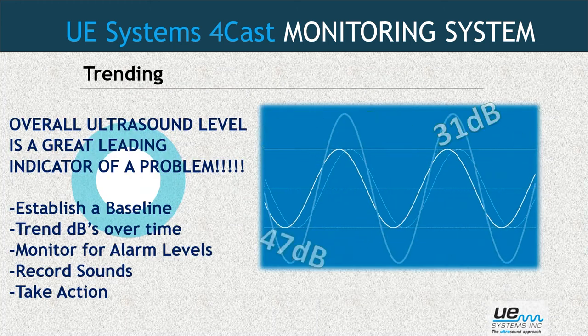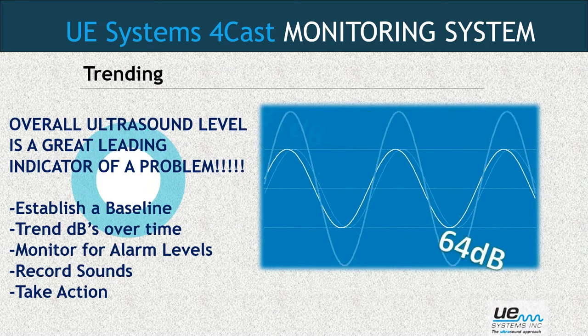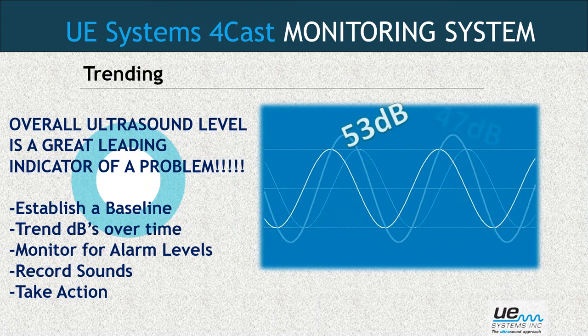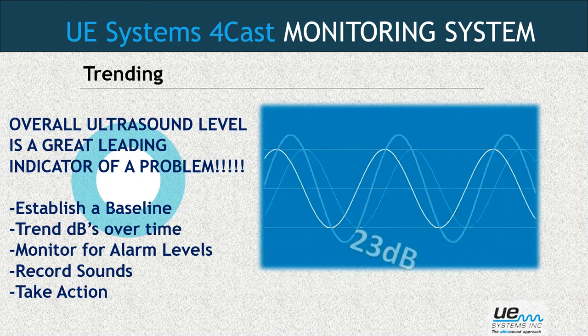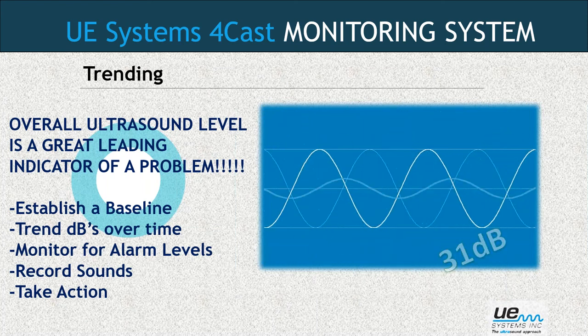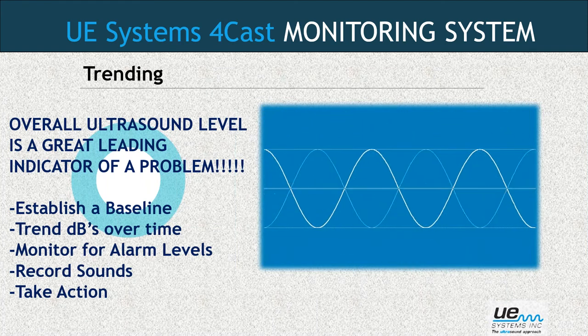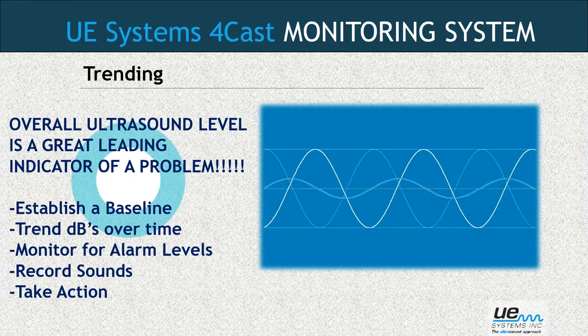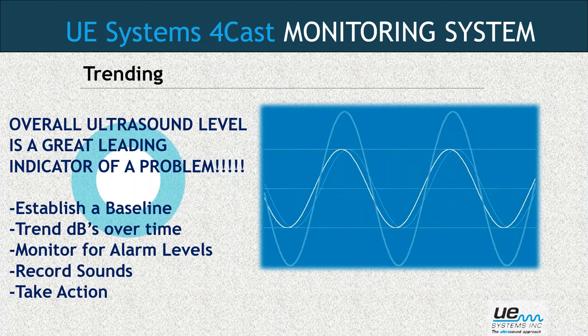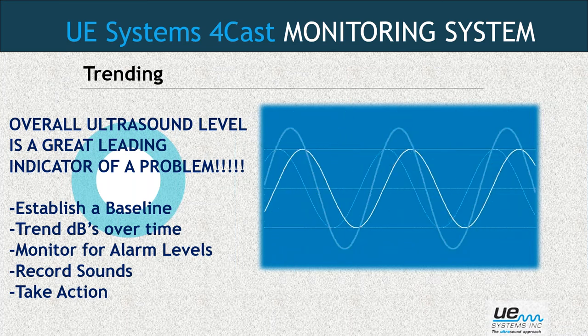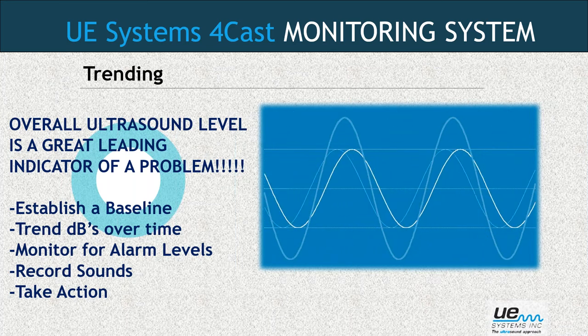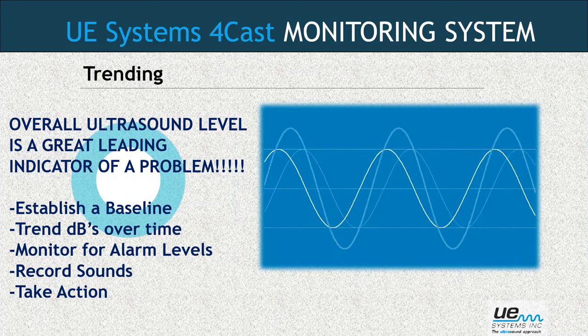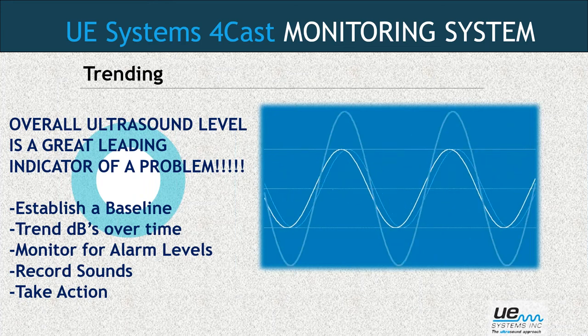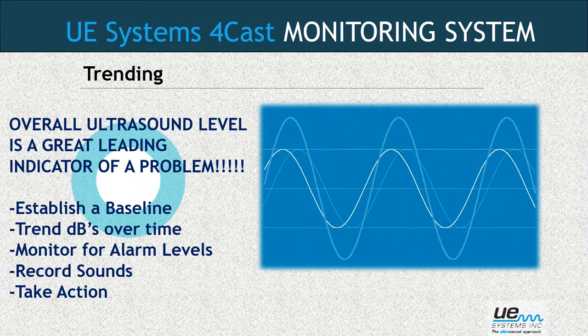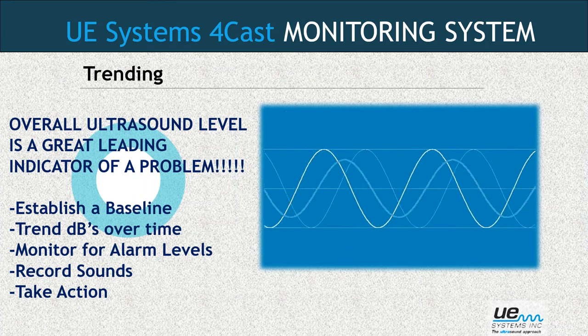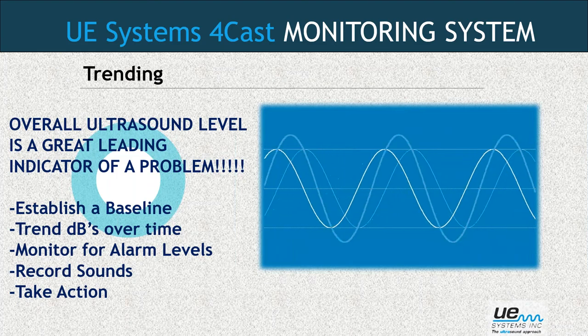We live in the world of decibels. That's really the numbers that we're using to measure an increase in the sound level. And it turns out that measuring the increase in dB over time makes ultrasound a great leading indicator that there's a problem. Just the overall ultrasound level, the overall number, once you've established a baseline, makes it really easy to trend these over time. We're also able to monitor for alarm levels.